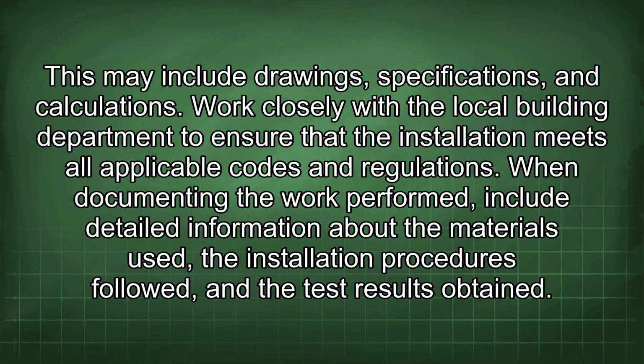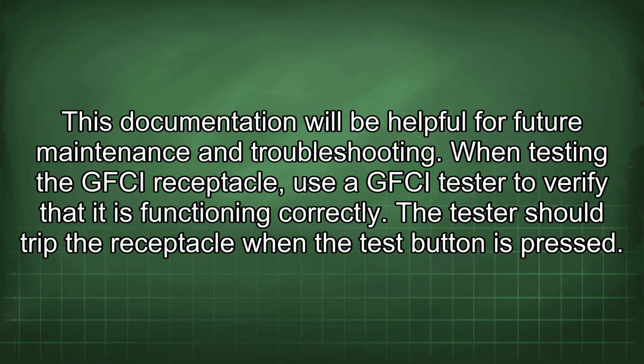When documenting the work performed, include detailed information about the materials used, the installation procedures followed, and the test results obtained. This documentation will be helpful for future maintenance and troubleshooting. When testing the GFCI receptacle, use a GFCI tester to verify that it is functioning correctly. The tester should trip the receptacle when the test button is pressed.